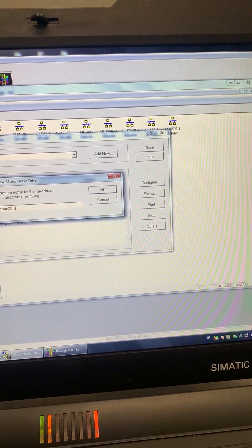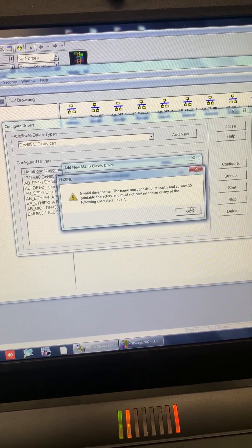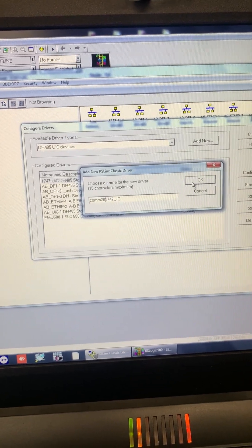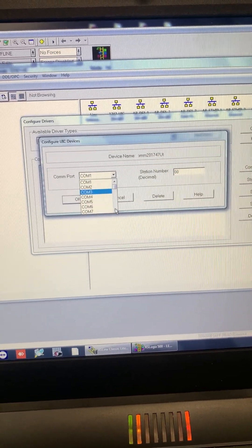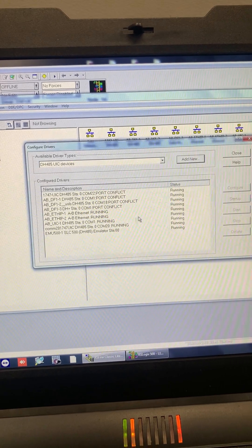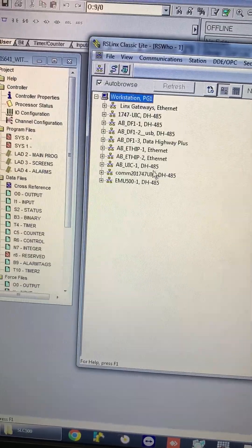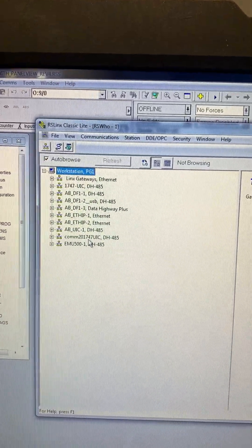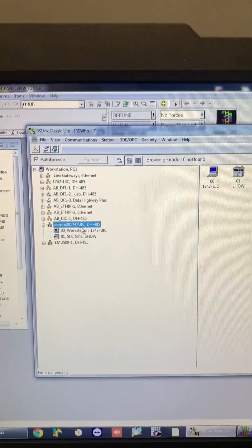Change the name. COM 20. 1747 UIC. We need to change the COM port. Our COM port is 20. We looked at the device manager. Choose COM20. Close it. And here we have COM20, 1747 UICs, RSLinx. Choose it. And here's our PLC.